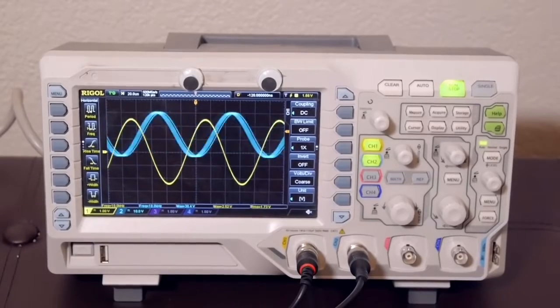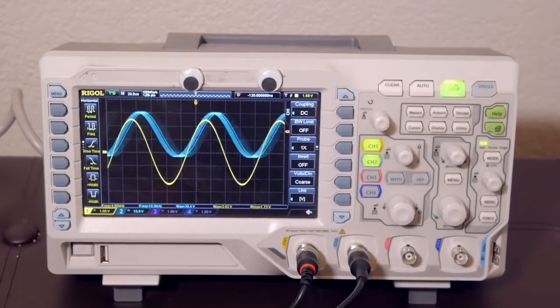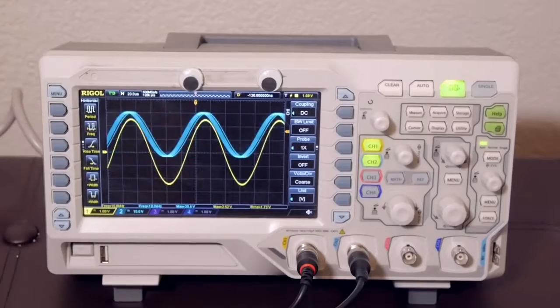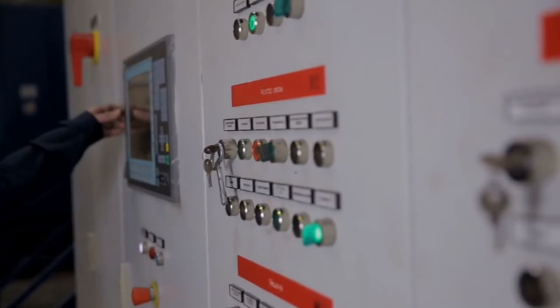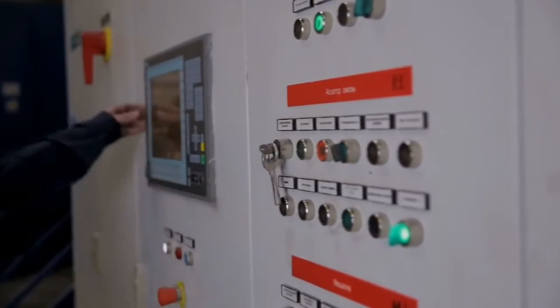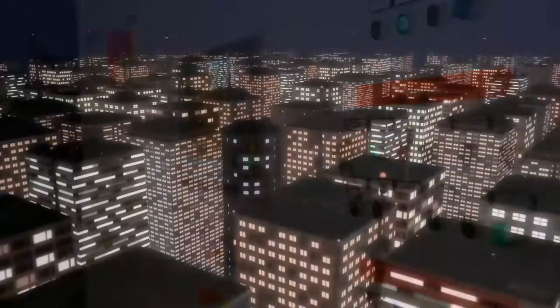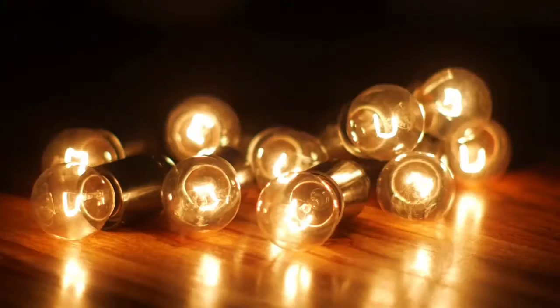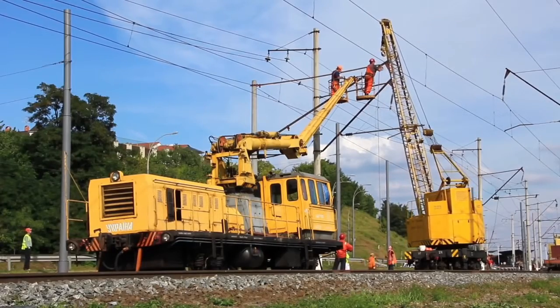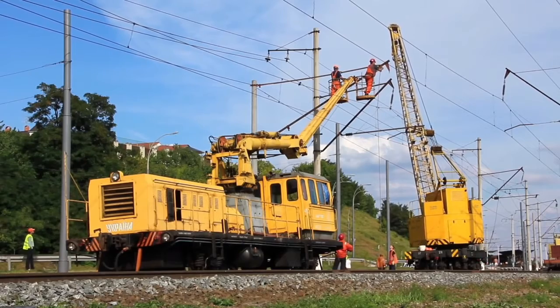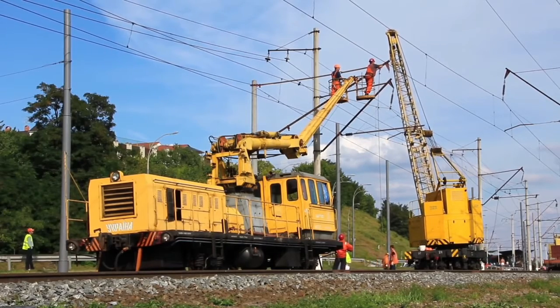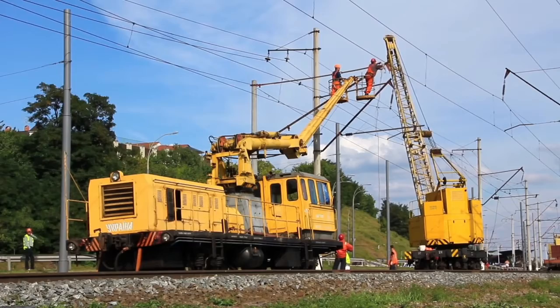Relays also keep an eye on the frequency of the grid to make sure different components don't lose synchronization. Certain breakers can also be manually activated, like during rolling blackouts, where utilities are forced to shed non-critical electrical loads due to lack of generation capacity. These are all types of managed failures, where you have some loss of service at the cost of protecting the rest of the system. The goal is that isolating equipment when things go wrong speeds up the process and reduces the cost of making repairs to get customers back online.